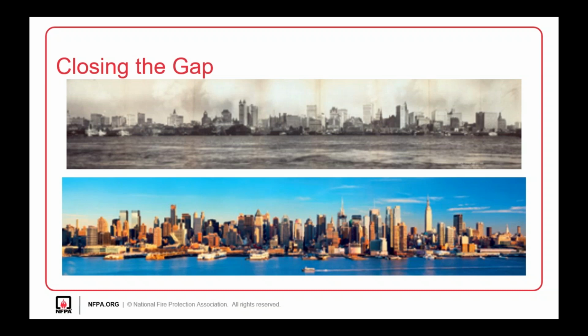This is important because even today, we don't rely on one specific system to detect, notify, or suppress. We rely on all these systems together to allow us to safely egress a building in the event of an emergency. NFPA 4 mandates that systems intended to function together are actually tested to ensure the interaction, operation, and coordination of multiple integrated systems are functioning properly.